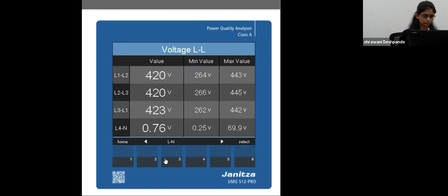Now the next screen is a voltage screen, in which we can see the line voltages and phase voltages. So this is the screen showing line and phase voltages. Now if we select on this, we can see that it is showing the total harmonic distortion, power factor, and frequency for each phase. Also, we can have the minimum and maximum values with timestamp. For example, if we select on this, we can see that my minimum value occurred at this time and on this date. Similarly, we can have this for line voltages also. So these are the line voltages.